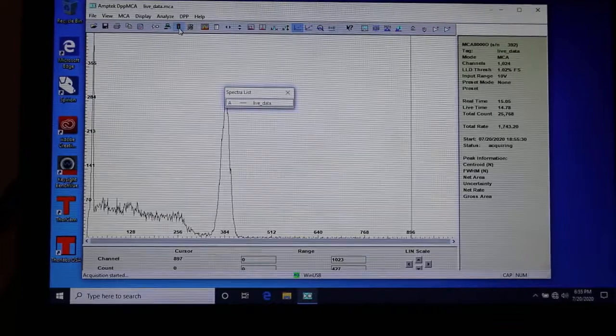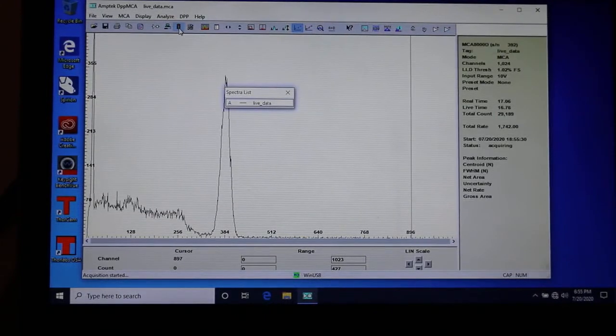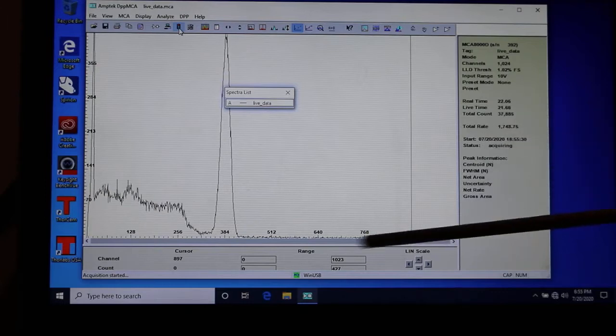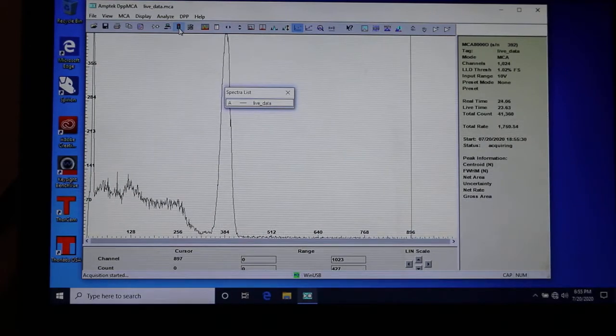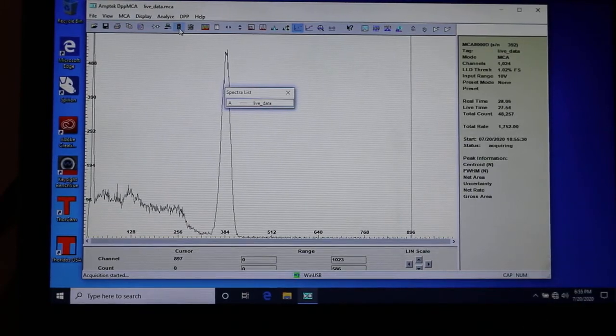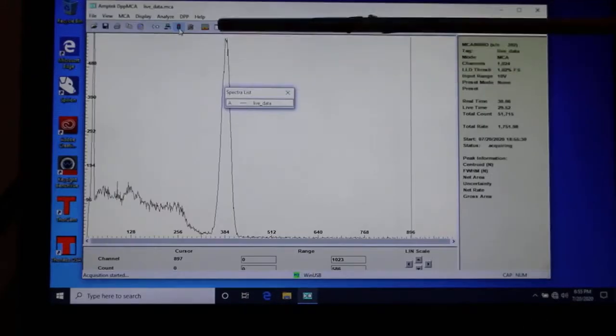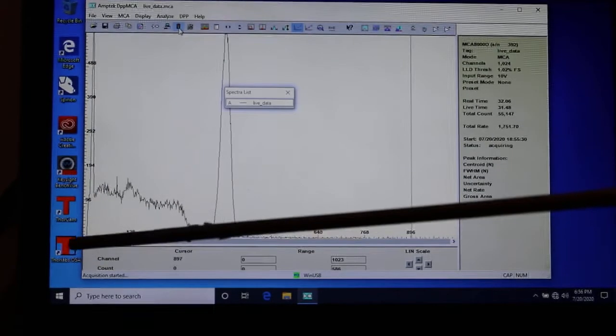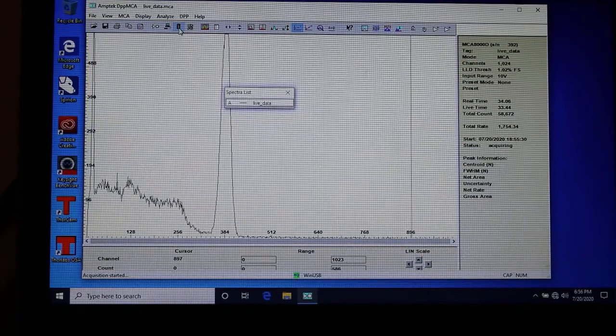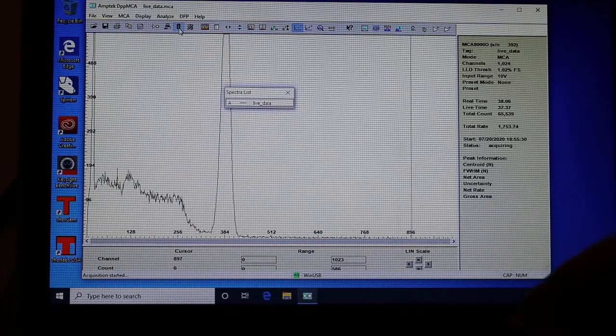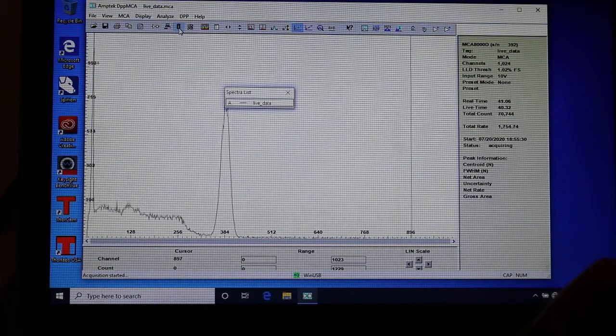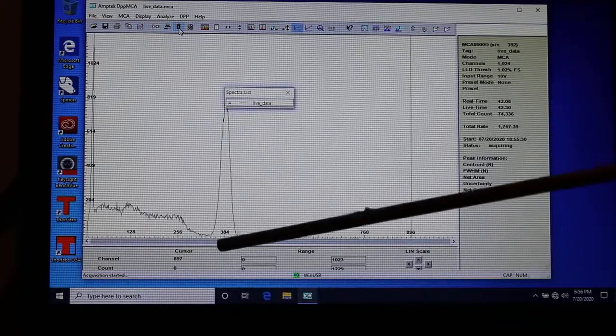We have several gamma ray sources that we're going to run through the system, and what we're aiming to do is get these channels calibrated into energy. That's a big outcome of this lab. So we want to produce a graph of, say, a cesium-137 spectrum where the x-axis is not in channels but in energy, a good physical parameter. We don't want to read channel 384.